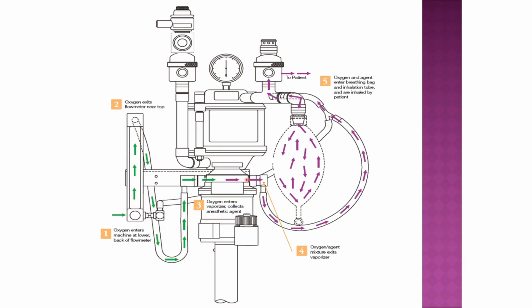And so the only purpose of the oxygen is to carry those anesthetic molecules and carry those gases through. So the higher your oxygen flow rates, the more anesthetic molecules you can pick up, and the faster your plane changes are going to occur. And this makes sense to me. If you're trying to fill your sink and you have your water on a little trickle, it's going to take a lot longer to fill that sink than if you turn that water on full blast. So for fast plane changes, we're always going to want to turn our vaporizer setting up and turn our oxygen flow up. And then it's going to come out here.